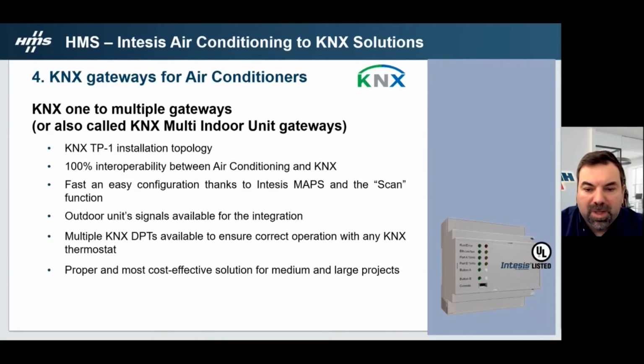The KNX one-to-multiple gateways, or also called the KNX multi-indoor unit gateways, are installed according to the KNX TP1 topology. It grants 100% communication between air conditioning and KNX. It comes with a fast and easy configuration thanks to the Intesis MAPS and the scan function. The main advantage of these gateways is because they have access to the outdoor unit signals. And as the one-to-one gateways, these KNX multi-indoor unit gateways also have the multiple KNX data points available to ensure correct operation with any KNX thermostat in the market. These interfaces are the proper and most cost-effective solution for the medium and large projects.